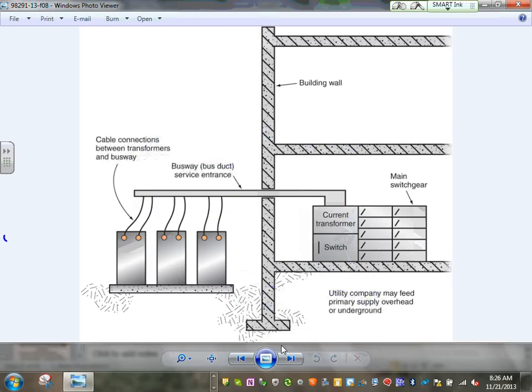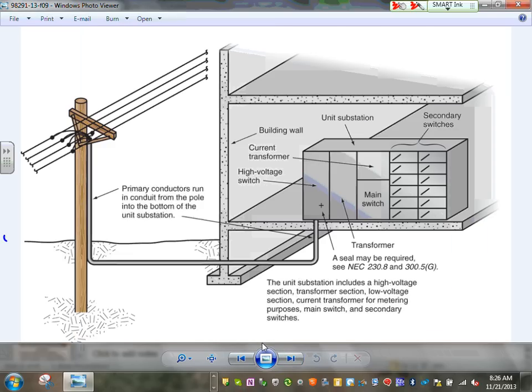Here's a couple of examples of bringing your service to the building. So here's my transformer. We are bus ducting it all the way to the CT. Here's current transformers. The current transformers that convert it so I can measure it. That's one way, industrial. So hold your horses on that one, because that's typically for industrial. Here's a commercial building where you bring the power directly from the service all the way into the building. You have current transformers, high voltage switch here, and you have current transformers here to meter it.